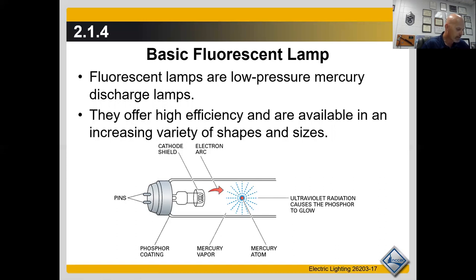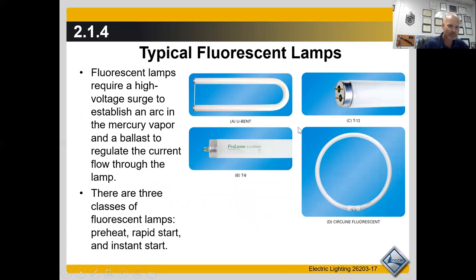Fluorescent bulbs are made in straight, U-bend, circular, and compact varieties. They are designated by the letter T followed by the diameter in eighths of an inch, ranging from T5 to T17 in the United States. Straight fluorescent lamps range from six inches up to eight feet in length. Higher wattages go with longer bulbs — for example, a 20-watt T12 tube is shorter than a 40-watt T12 tube.